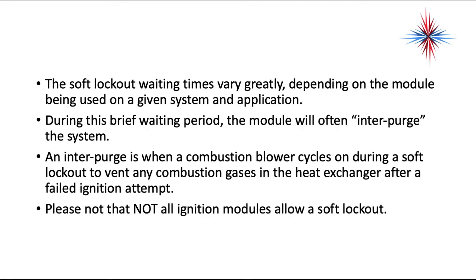The soft lockout waiting times vary greatly depending on the module being used on a given system and application. During this brief waiting period, the module will often interpurge the system. Interpurging is when the combustion blower cycles on during a soft lockout to vent any combustion gases in the heat exchanger after a failed ignition attempt.